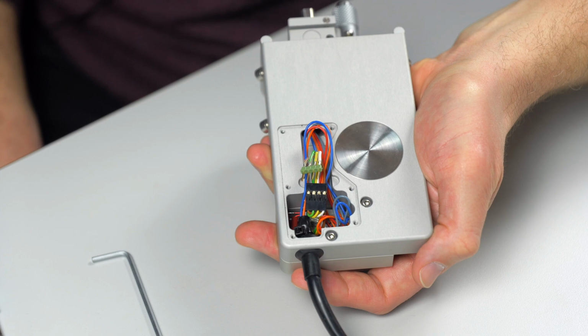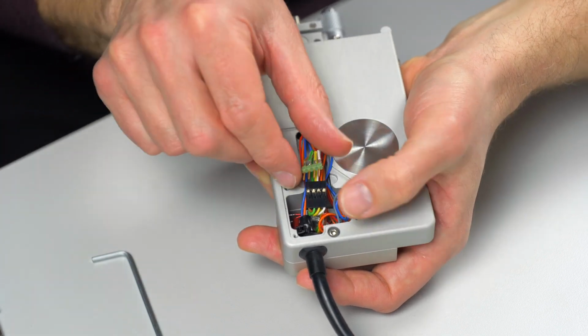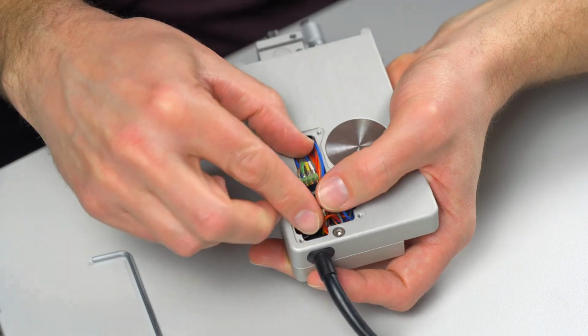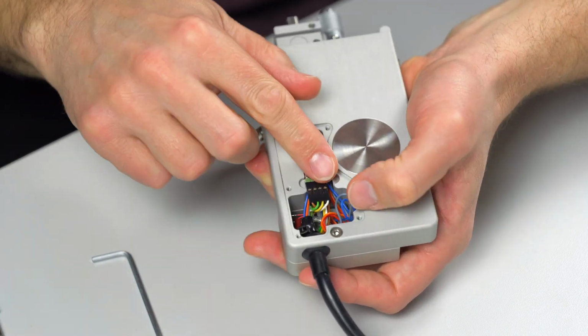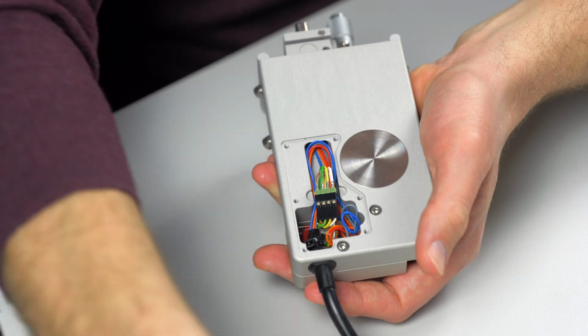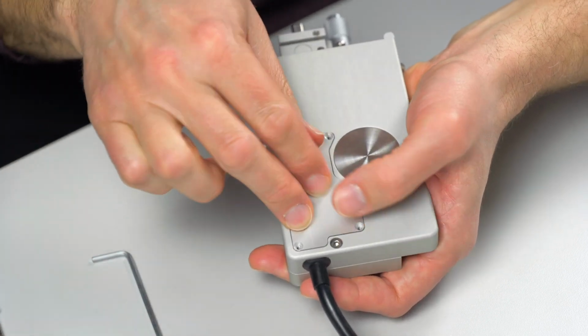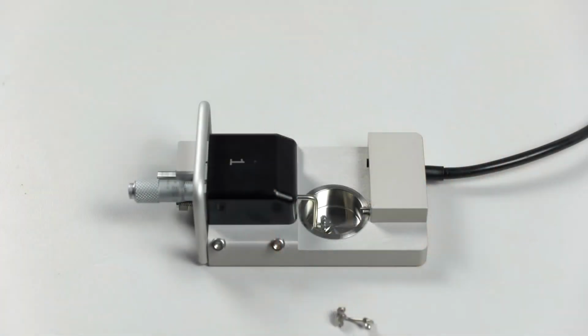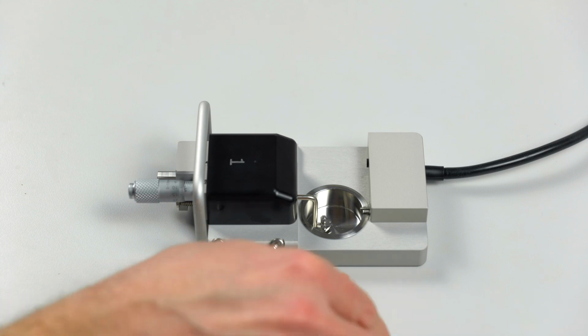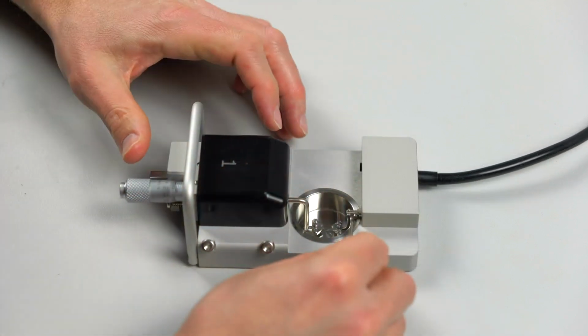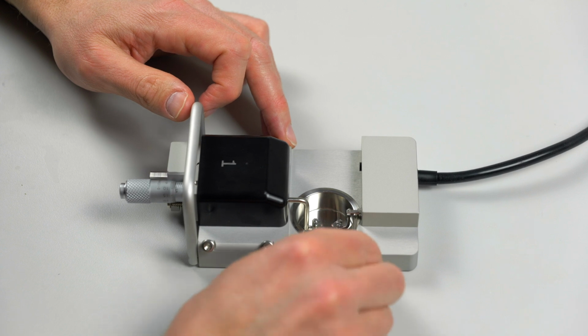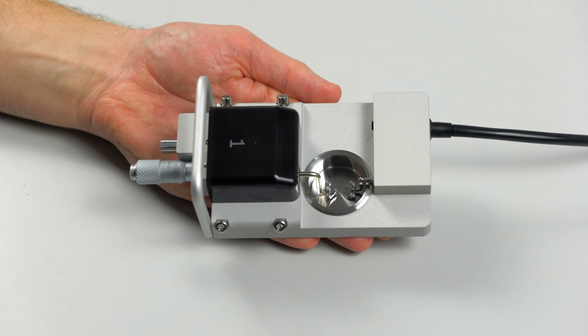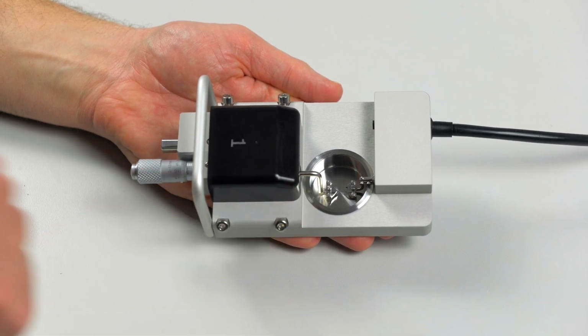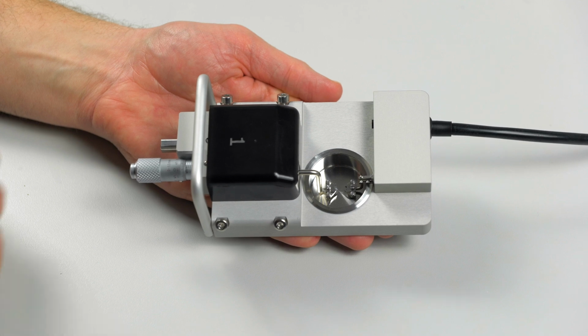Now that the transducer housing is securely in place, it's time to reconnect the cable connection. And remount the cover. Once all the screws have been tightened, you can flip your chamber over and reattach your mounting support. Once your mounting support is back on, you can then go to a microscope and align the supports and then calibrate your transducer, and you're ready to use.